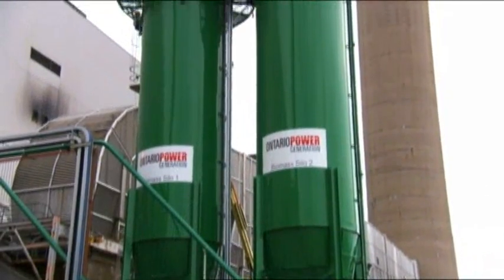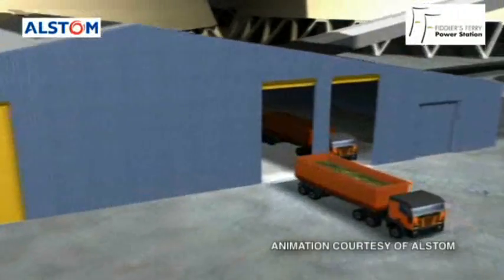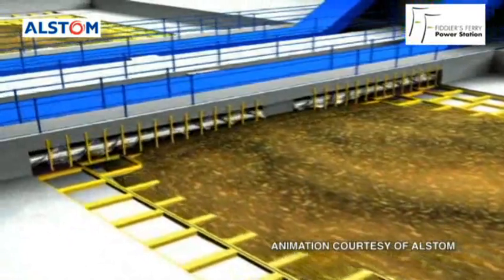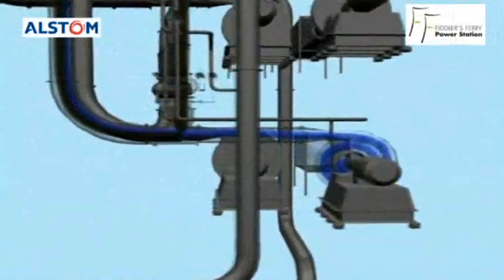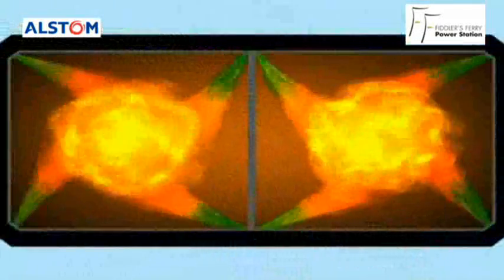The scale of the Nanticoke test equipment is small compared to some of the European plants. Most of the systems you'll see around the world are very similar — they involve a dedicated reception system designed to deliver ready-to-burn biomass feedstocks, and pneumatically inject dry, granular biomass feedstocks into existing piping that already carries coal to the furnace. The two streams mix together and are conveyed to the furnace to provide its energy input.